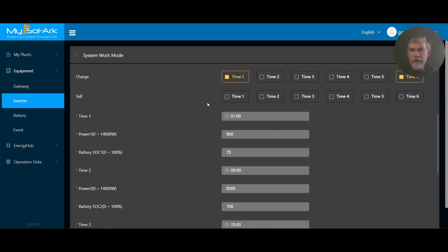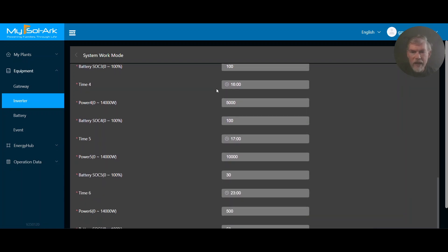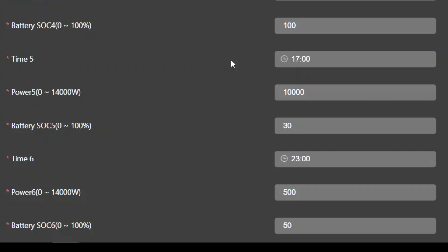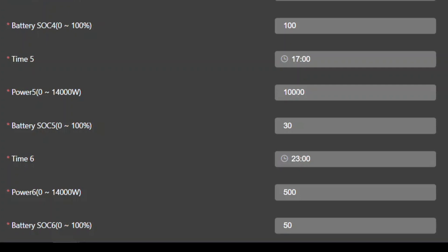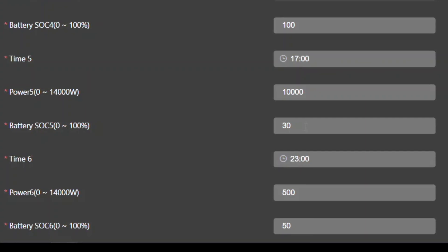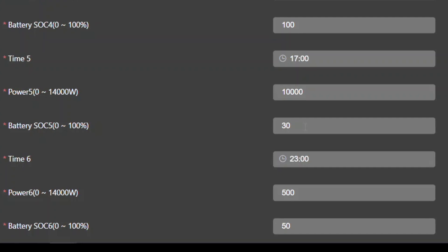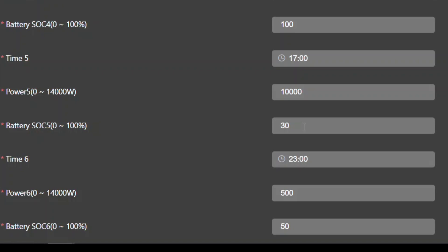The really interesting part about the time-of-use settings is that in each time zone, you're telling the battery where its state of charge should be. For example, at time zone five, starting at 5 p.m., you can discharge at up to 10 kilowatts and the battery needs to reach 30% SOC. Because sell is not checked, it won't just dump 10 kilowatts into the grid. Instead, it will cover any loads under 10 kilowatts until it reaches 30% SOC, and once it hits 30% SOC, it stops. Then it moves on to time zone six.